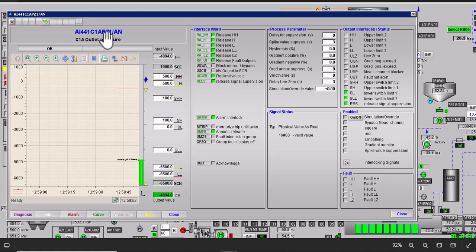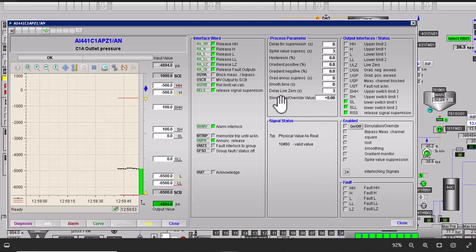Let me show you on the SCADA HMI all the values of the CMART block. This is how the CMART block values look on the HMI interface — the settings for HH, high, SHH, low, and low-low values, the real-time value, and release annunciation. The important parameters have been covered in this video. If you have any questions about the CMART block and its implementation in logic and HMI, you can ask in the comments. In upcoming videos we will be talking about additional CMART blocks and PCS7 blocks. Thanks for watching and see you in the next video.